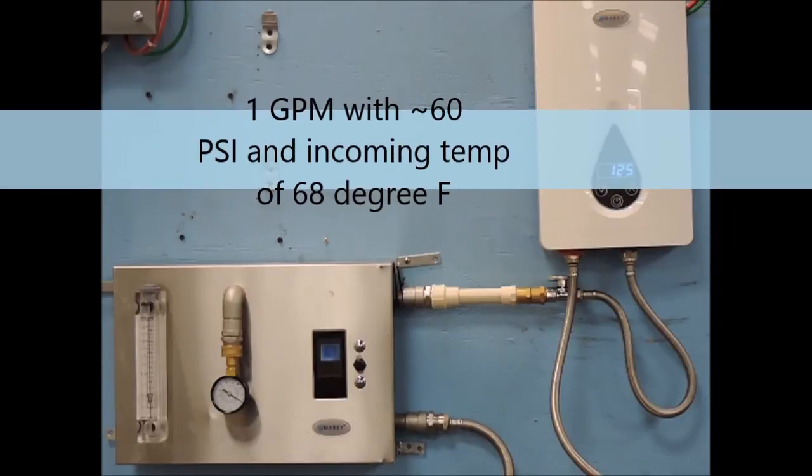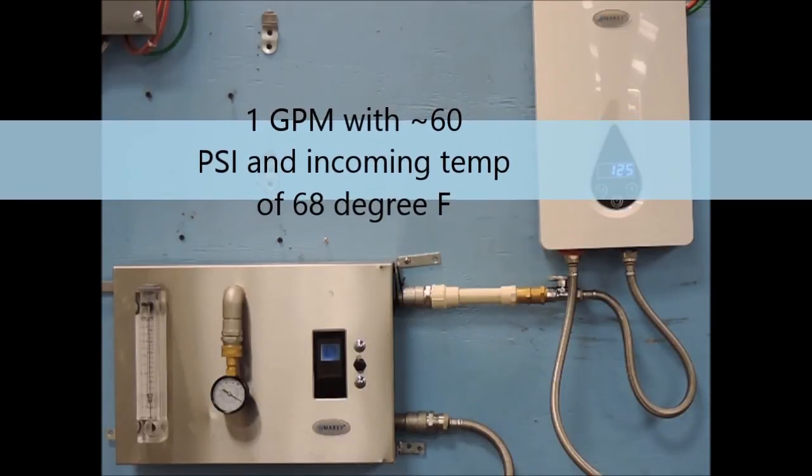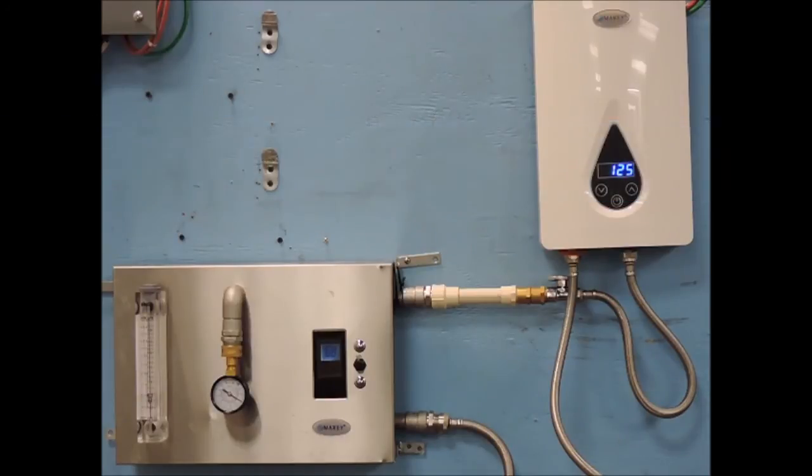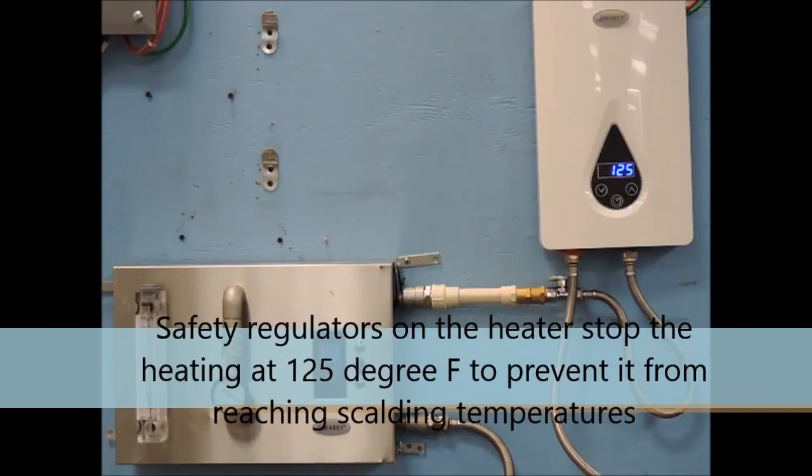Next, we bring the flow rate down to a gallon per minute, still with a psi of 60 and an incoming water temperature of 68 degrees. With these inputs, we are hitting the maximum set point for this unit, which is 125 degrees.